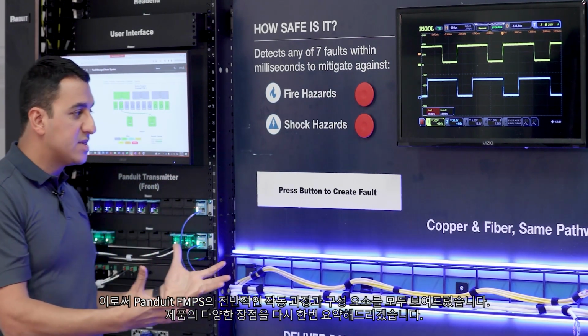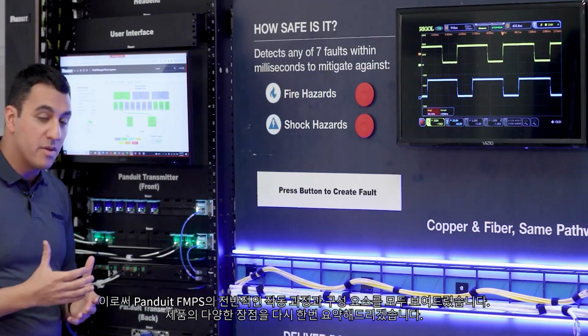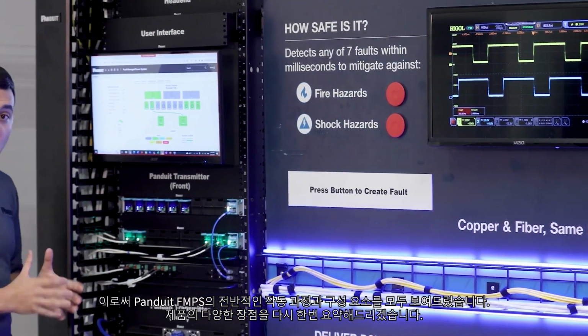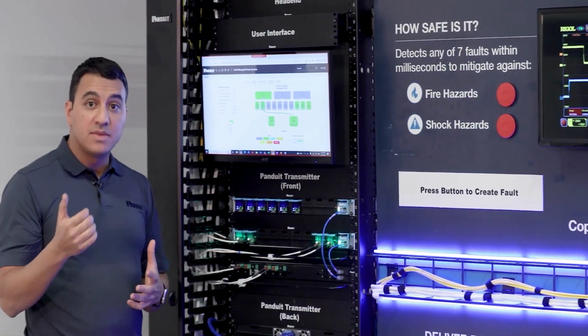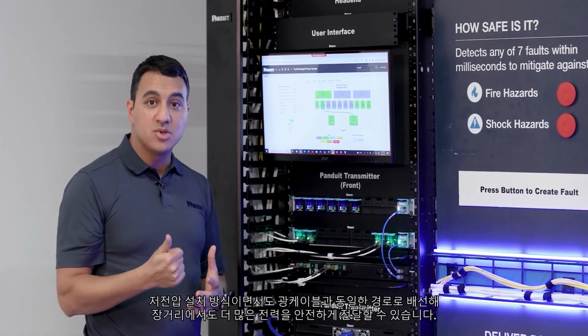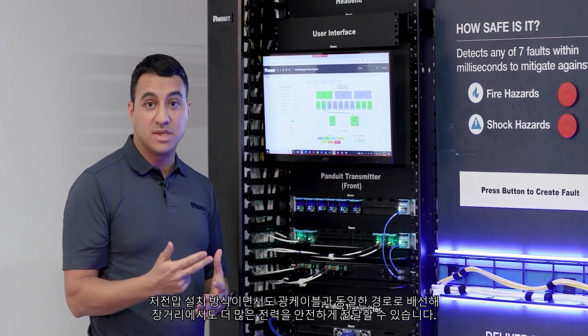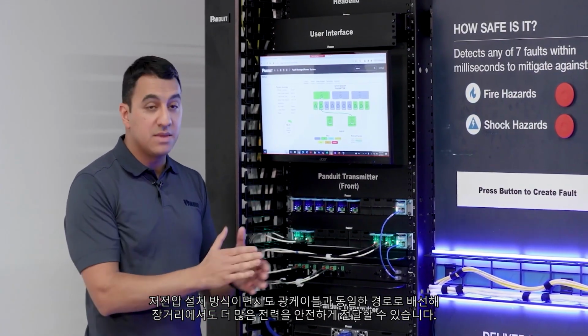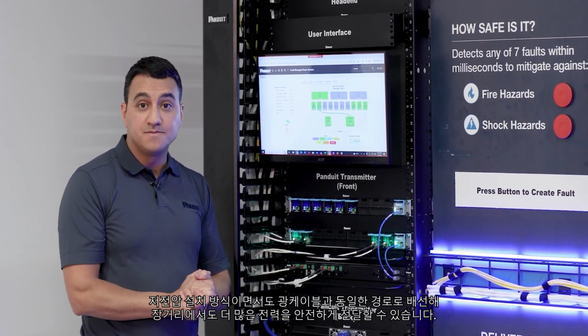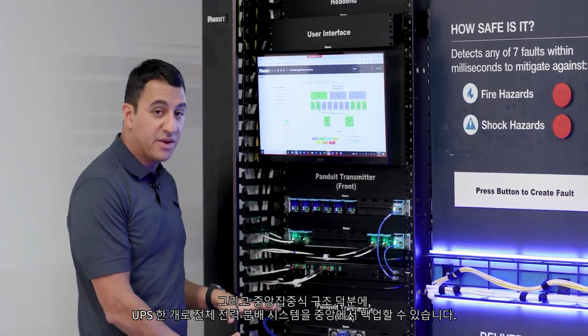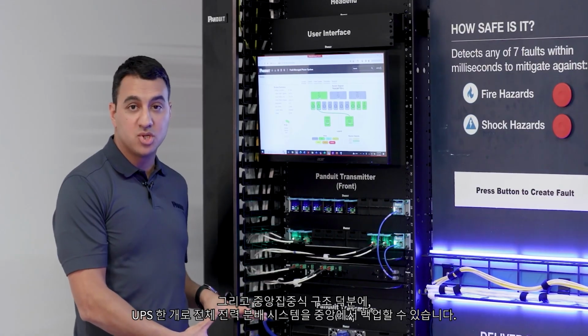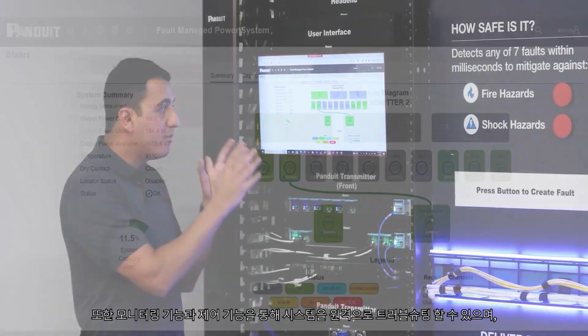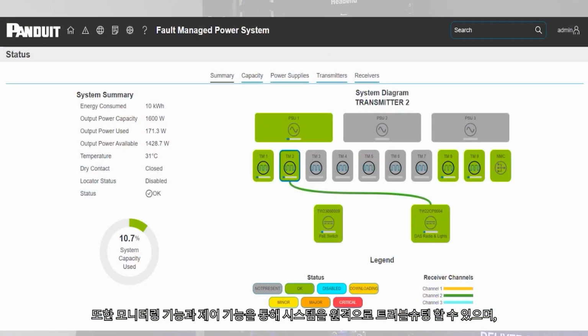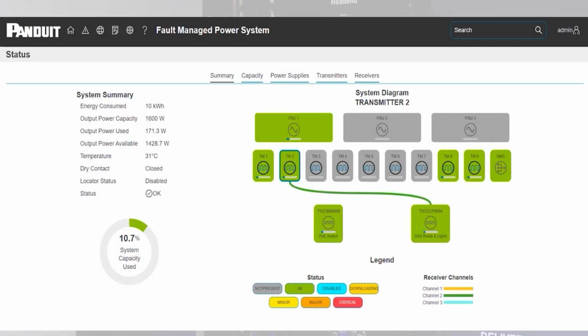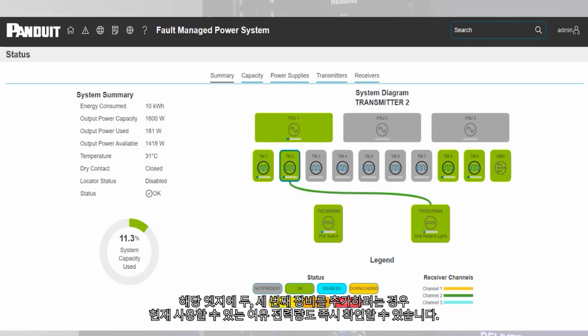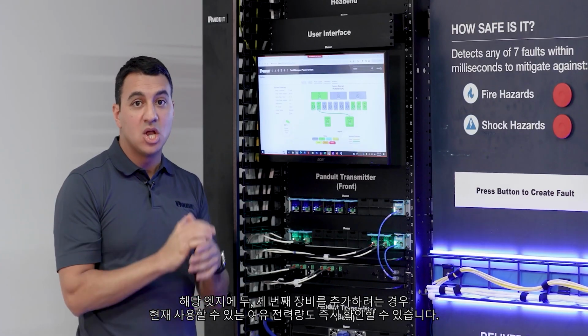This now represents and concludes how the Panduit fault managed power system works, the different components, and the benefits that you get: the low voltage installation while being able to push a lot more power over long distance safely by running it in the same pathway as your fiber. And you have the centralized benefits. You can centrally back up your power distribution with a single UPS. You have monitoring and control capabilities that allow you to troubleshoot your system remotely and tell how much power you still have available if you wanted to add a second or a third device to that receiver at the edge.